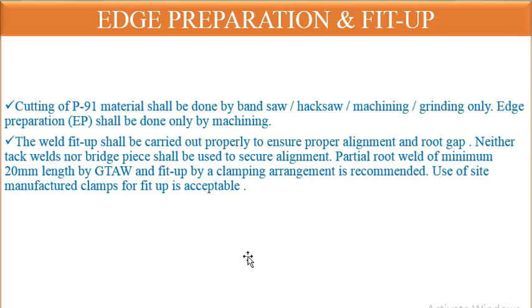For edge preparation and fit-up: cutting of P91 material shall be done by bandsaw, hacksaw, machining, or grinding only. Edge preparation shall be done only by machining — no other method is accepted. The weld fit-up shall be carried out properly to ensure proper alignment and root gap. Neither tack welds nor bridge piece shall be used to secure alignment.